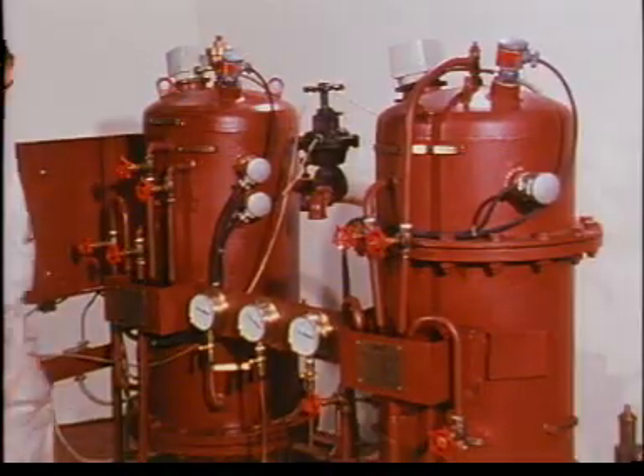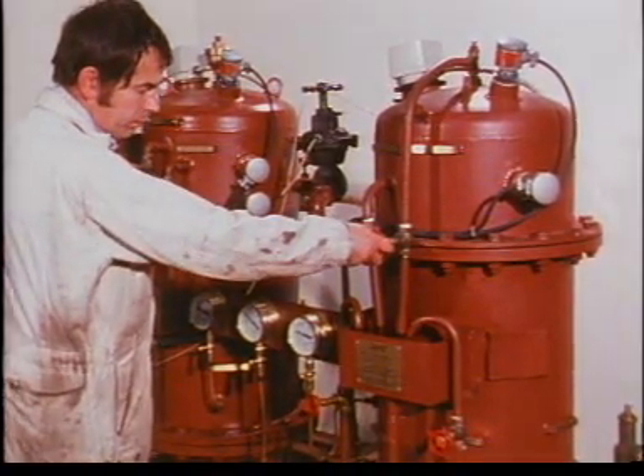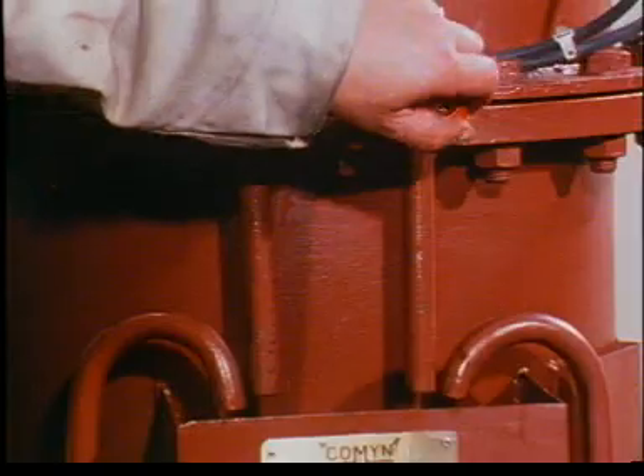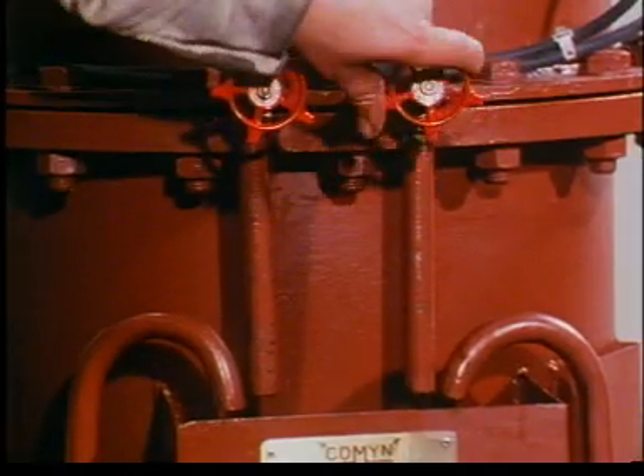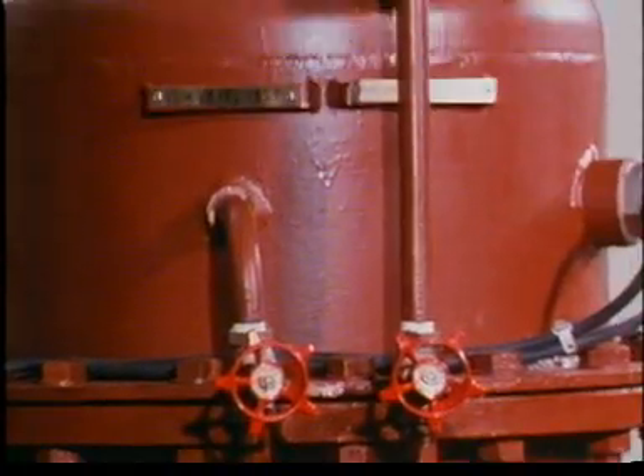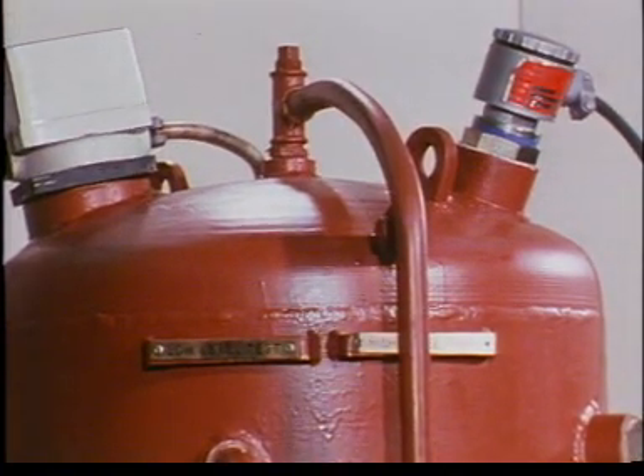Infrequently, probably about once a year, the coalescer elements will require replacing. As much oil as possible is evacuated from the coalescer. Use the high-level test valve, since this is connected to the extreme top of the dome.